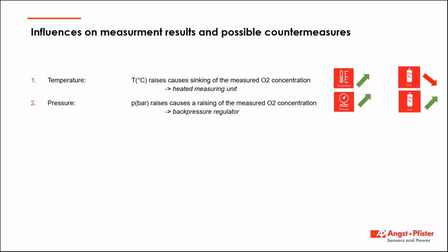It goes so far that, for example, a 10 millibar change of atmospheric or barometric pressure will cause, when you measure 100% oxygen, a 1% change in reading. Just to give you an idea. This can be compensated by a so-called back pressure regulator, where you regulate the pressure above the atmospheric pressure.